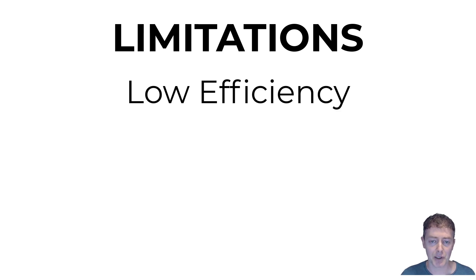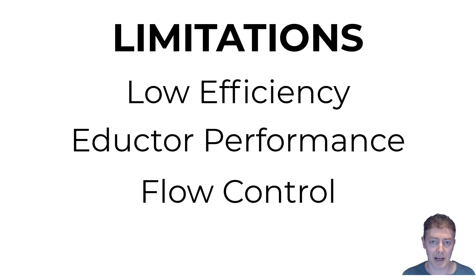However, eductors do have some limitations. They have quite a low efficiency compared to mechanical pumps, because we're converting energy from pressure to velocity and then back from velocity to pressure again — these conversions decrease overall efficiency. The performance of an eductor is directly dependent on the pressure and flow rate of the motive fluid; if there's a pressure drop or low flow rate, the eductor will no longer work. Controlling the flow through an eductor is also quite difficult, especially if the motive fluid flow is not stable. High viscosity fluids — those with a high resistance to flow — are also not best suited for an eductor, because the suction lift generated may not be strong enough to overcome their resistance to flow.